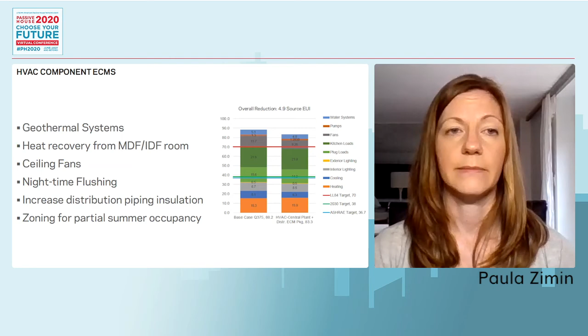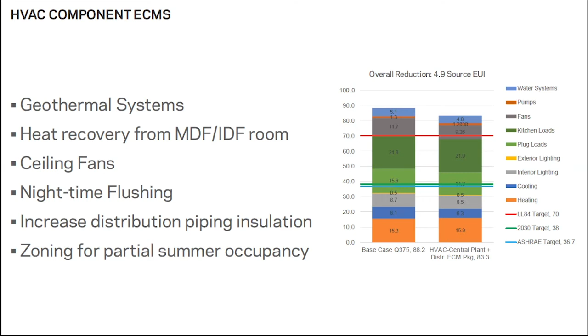In addition to additional HVAC components, we did look at geothermal systems. The original design did investigate geothermal energy piles. However, there wasn't sufficient room or sufficient energy available in the ground to pull and offset the energy use of the building. So it wasn't really feasible for this particular project. We investigated heat recovery from the MDF and IDF rooms, ceiling fans, increasing the distribution of piping insulation, which we applied, and as we said, the zoning. So all of the accepted ECMs reduced the total source EUI by about 5, which we thought was a success.